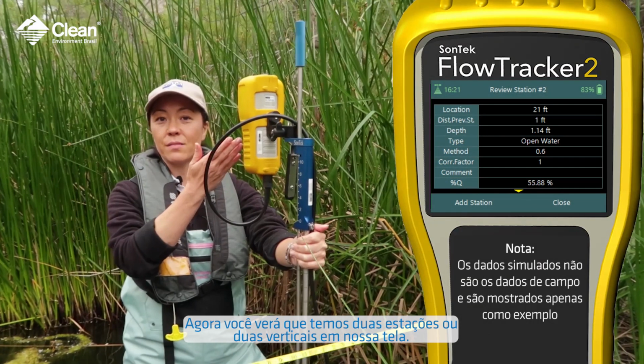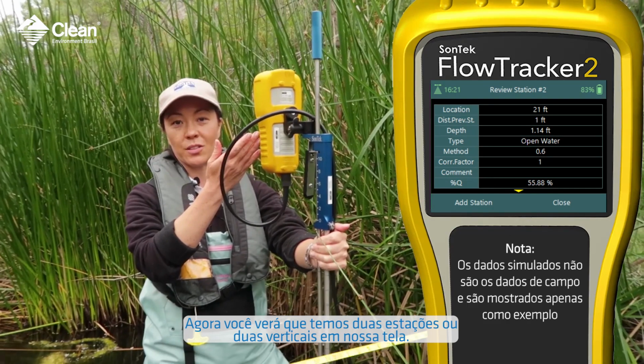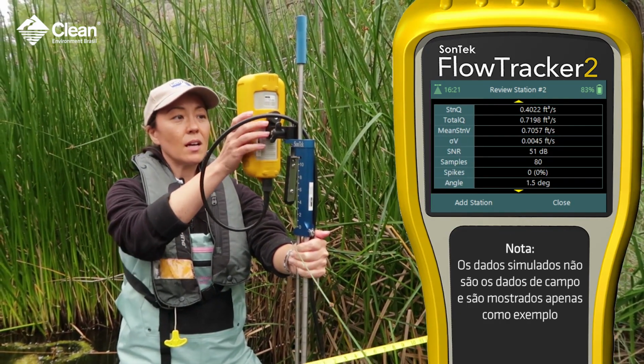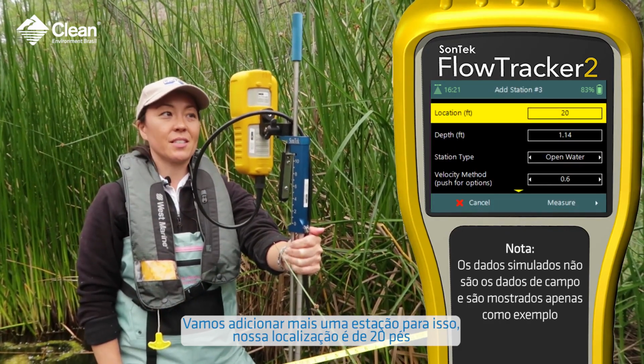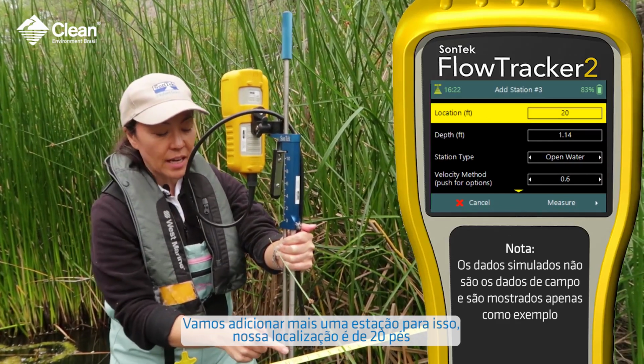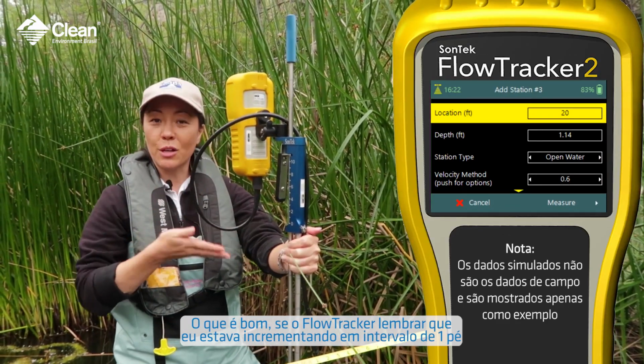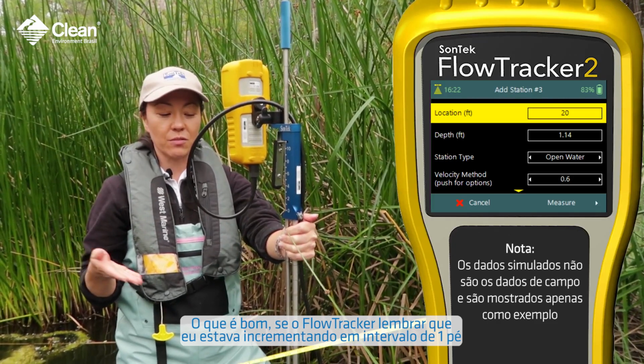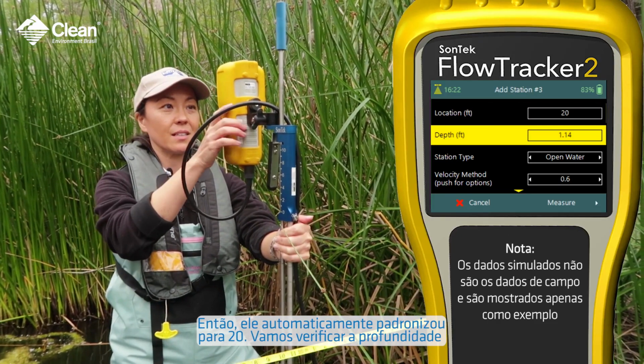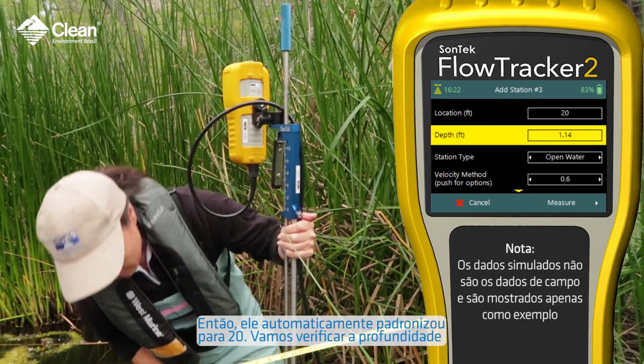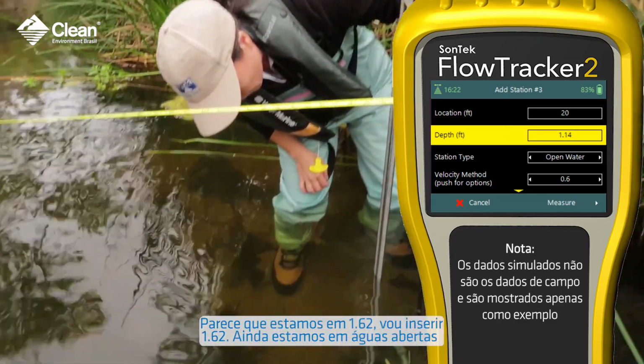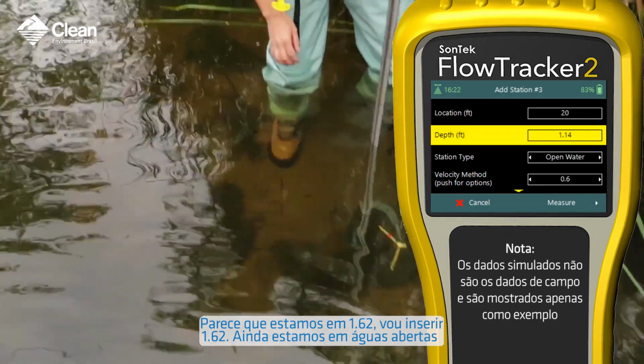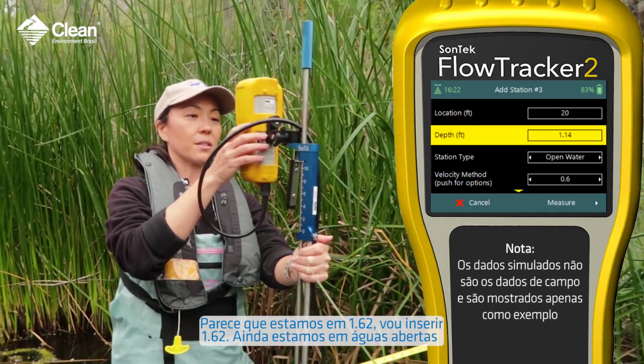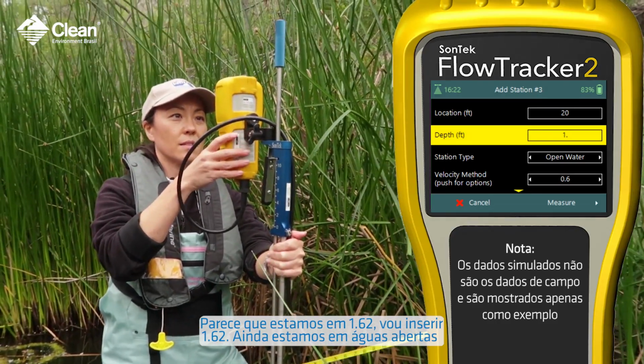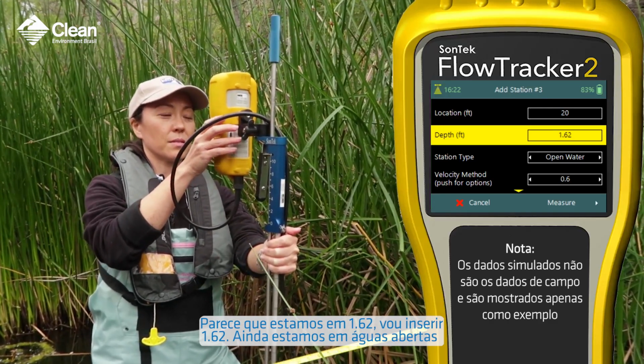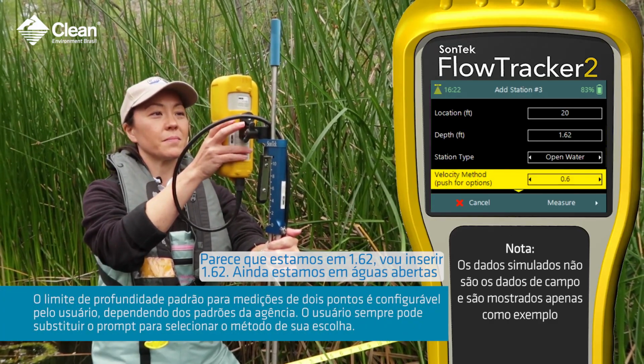Now you'll see we have two stations or two verticals on our screen. Let's add one more station. For this, our location is 20 feet. What's nice is that the FlowTracker remembered I was incrementing in 1 foot intervals, so it automatically defaulted to 20. Let's check the depth. It looks like we're at 1.62. So I'm going to enter 1.62. We're still in open water.